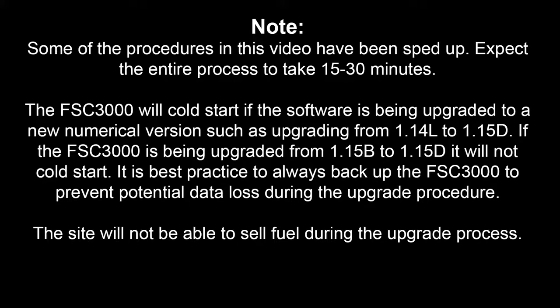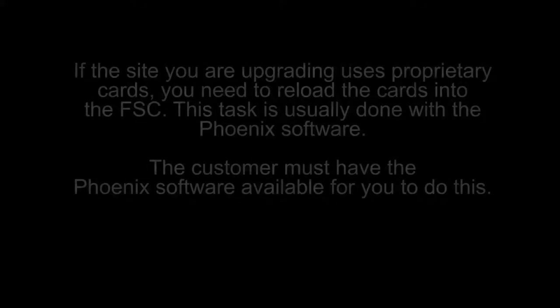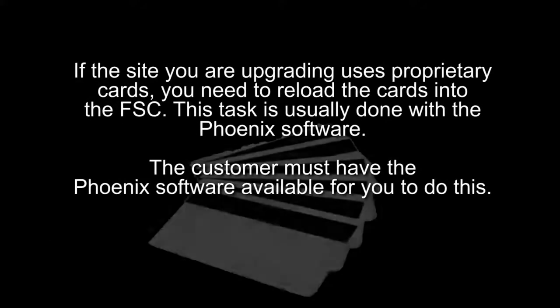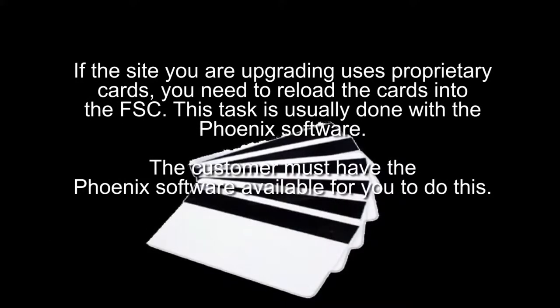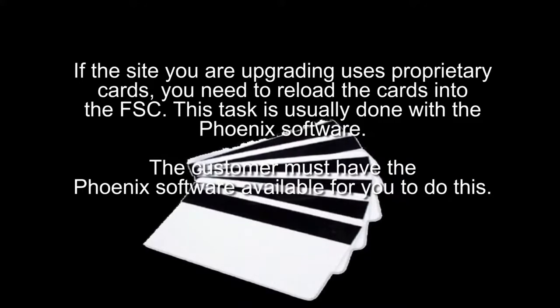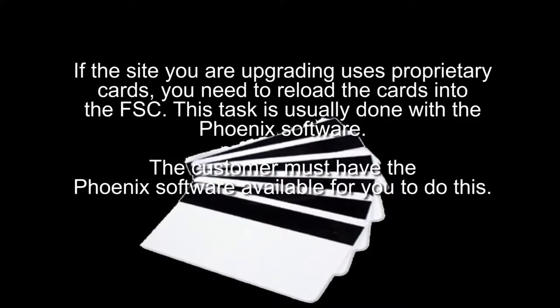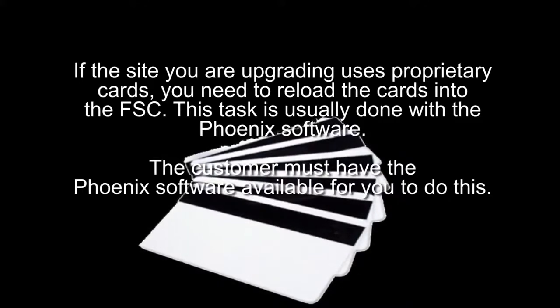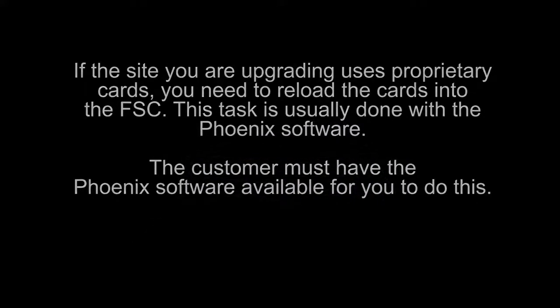The site will not be able to sell fuel during the upgrade process. If the site you are upgrading uses proprietary cards, you need to reload the cards into the FSC controller. This task is usually done with the Phoenix software. The customer must have the Phoenix software available for you to do this.